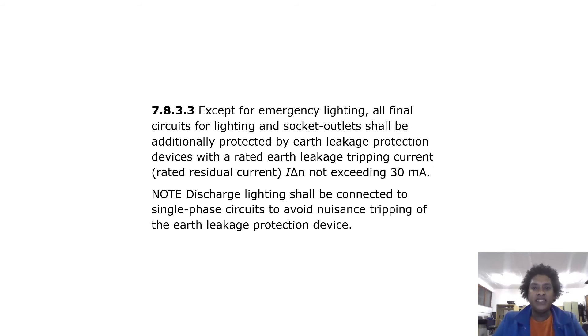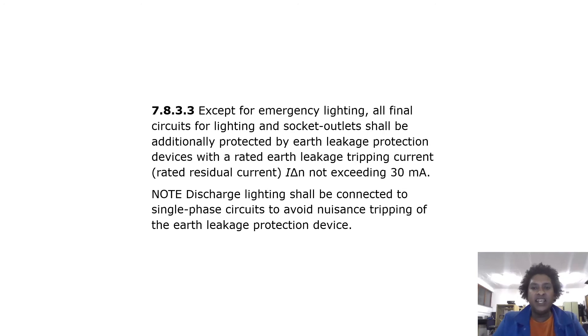Except for emergency lighting, all final circuits for lighting and socket outlets shall be additionally protected by earth leakage protection devices with a rated earth leakage tripping current not exceeding 30 milliamps. Note: discharge lighting shall be connected to single-phase circuits to avoid nuisance tripping of the earth leakage protection device.